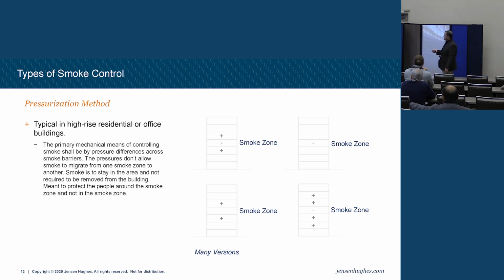Some of the older systems, they would just pressurize the floor above and floor below. This was pretty common too. So these two are probably the most common methods for really tall high-rises. You pressurize multiple floors above, multiple floors below, and then negatively pressurize the fire floor. The objective there being keep the fire on that floor, but evacuate all of those floors that are in the exhaust mode or in the smoke control mode. So in this example, I would evacuate all 3 of those floors.